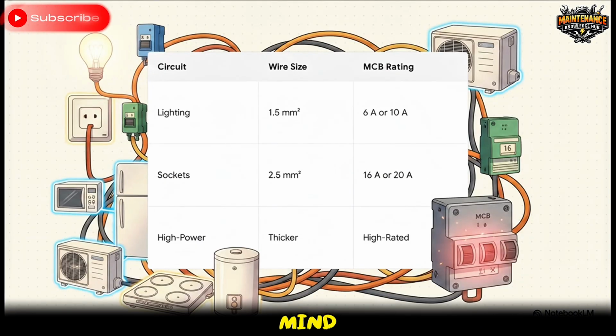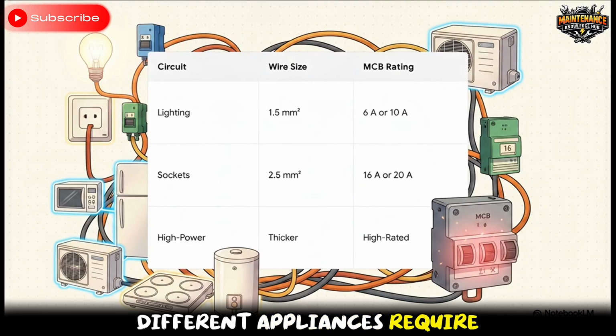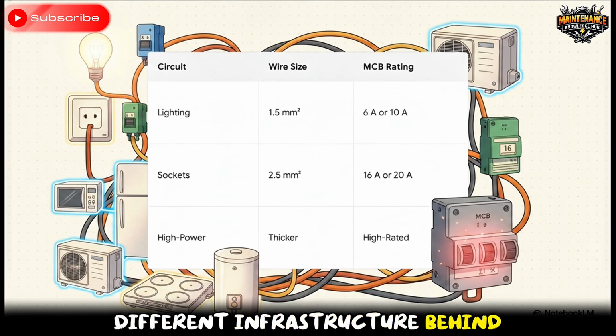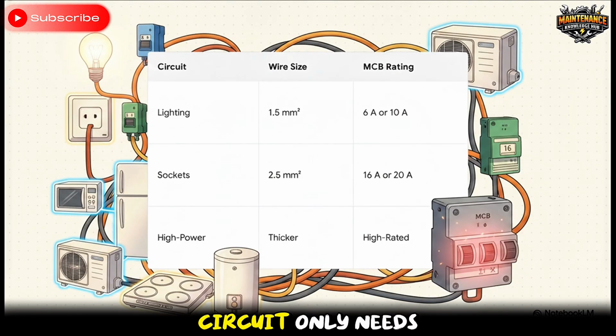But keep in mind, not all switches and circuits are created equal. Different appliances require drastically different infrastructure behind the drywall. A simple lighting circuit only needs relatively thin, 1.5 square millimeter copper wire, and a small 6 or 10 amp MCB. But your wall sockets, the ones that might run a fridge or a microwave, need thicker 2.5 square millimeter wire and a 16 or 20 amp MCB.